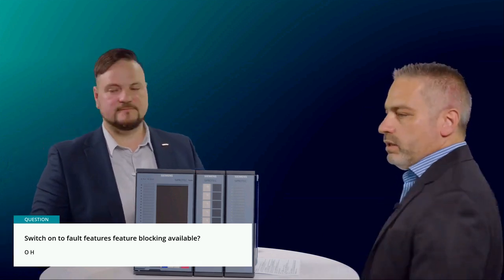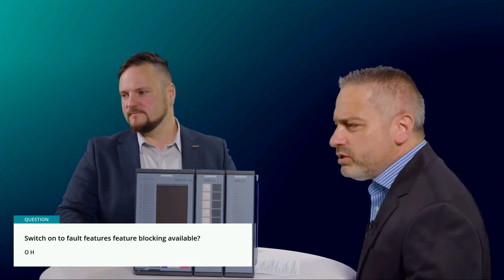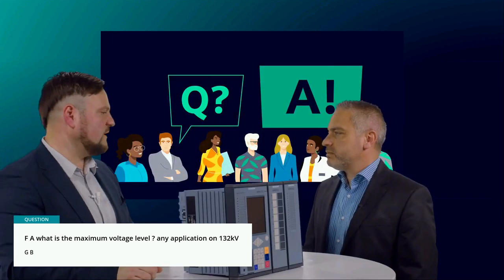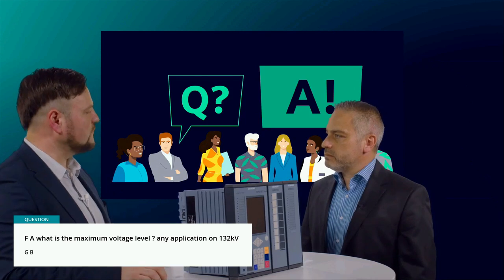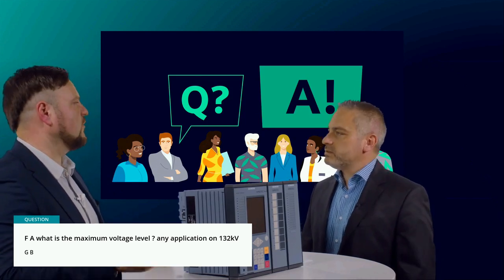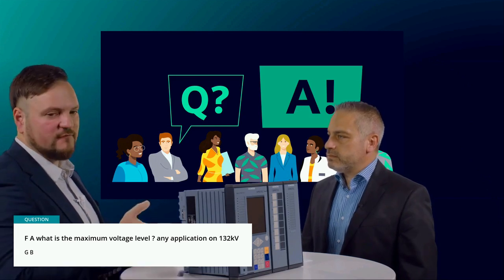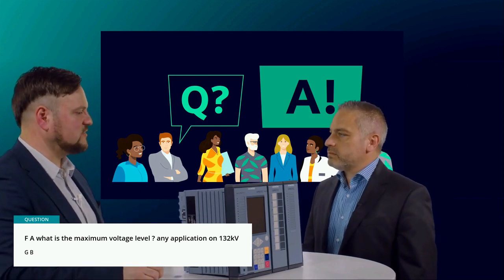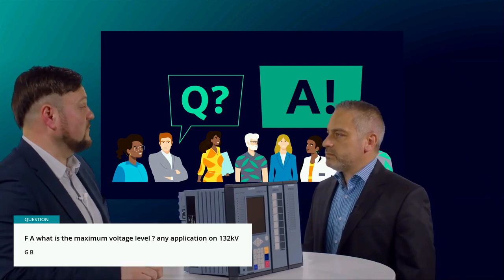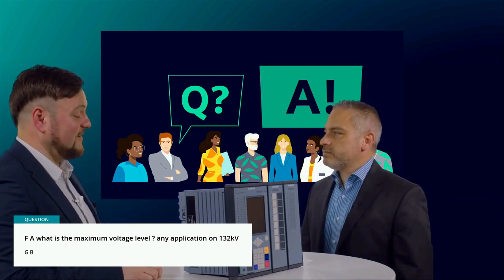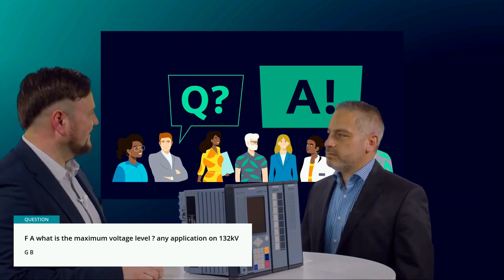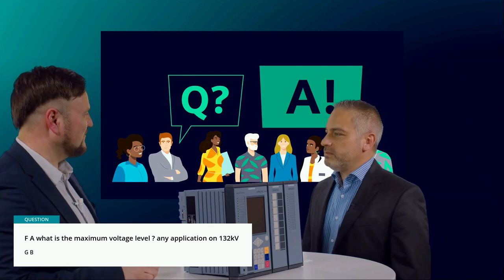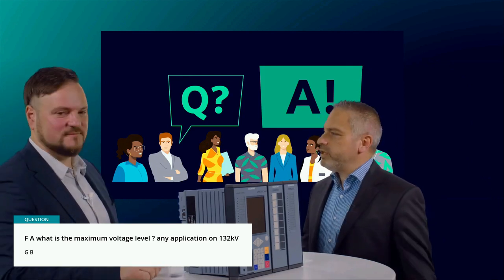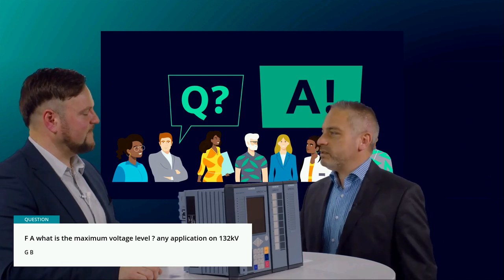What is the maximum voltage level? Do we have any applications at 132 kV? It depends on the application. Mainly, the HSBT function is used where we have motors on the bus, and this is normally in medium voltage applications. Of course, we have no limit for any voltage level, so there are no restrictions. You can use it for 400 kV, but I cannot imagine that at that level we have motors or inductive motors on the bus. So there is no restriction, theoretically possible, but not the standard case.